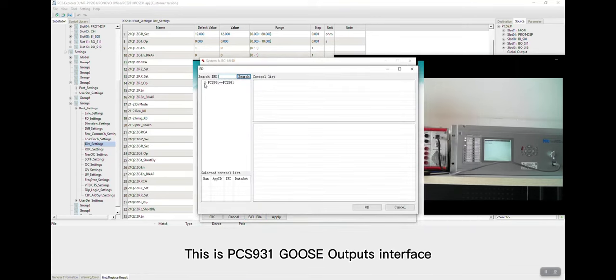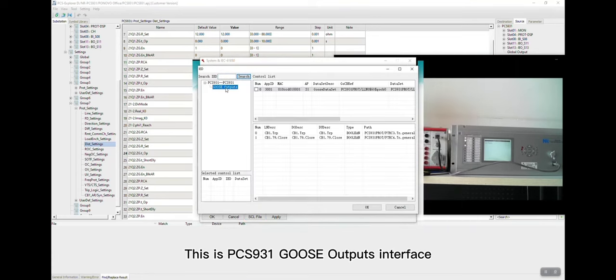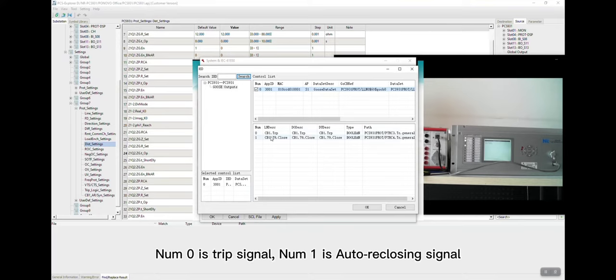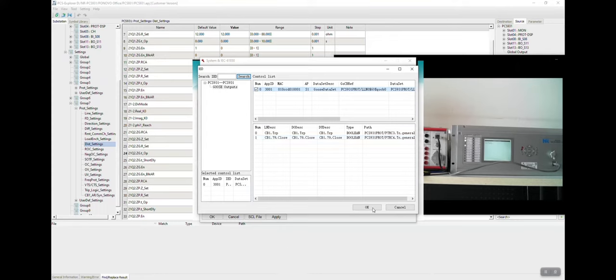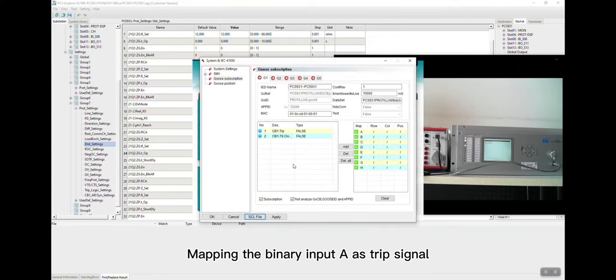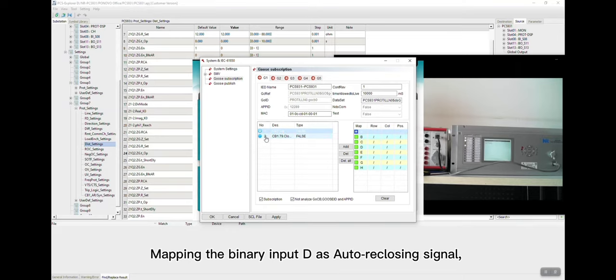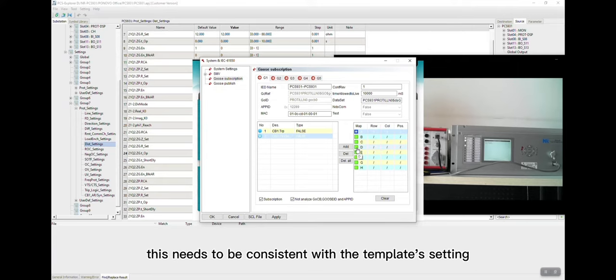This is the PCS931 Goose output interface. No.0 is trip signal, No.1 is auto-reclosing signal. Mapping the binary input A as trip signal, mapping the binary input D as auto-reclosing signal. This needs to be consistent with the template setting.